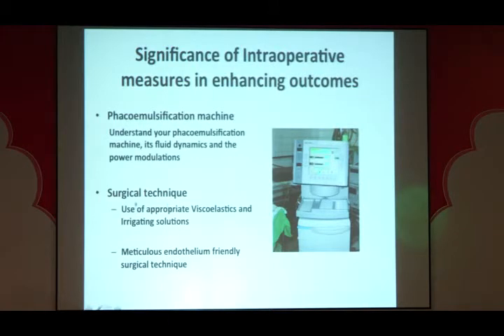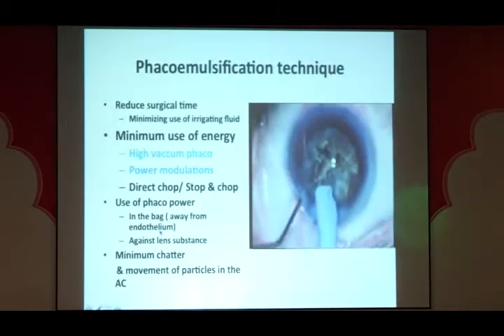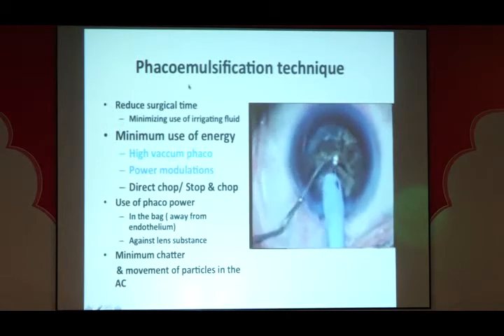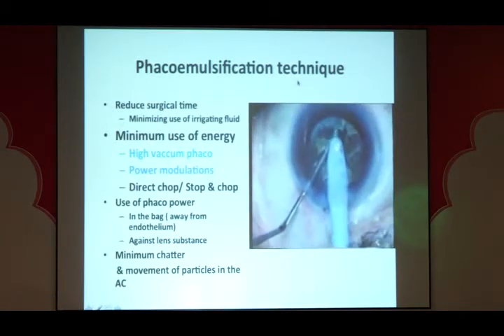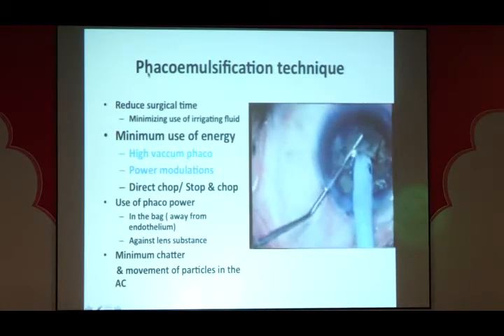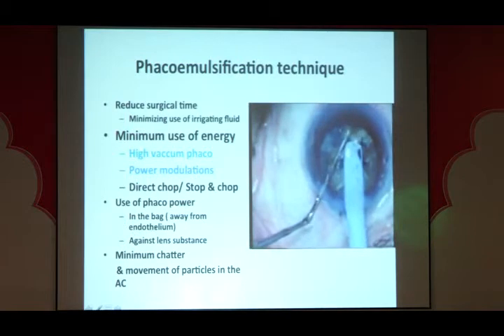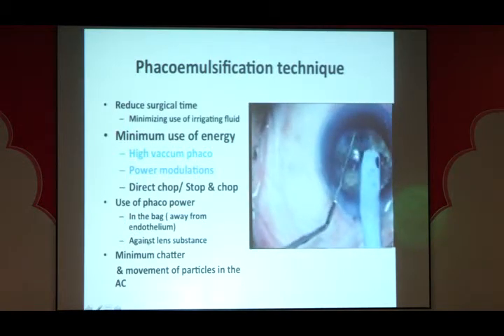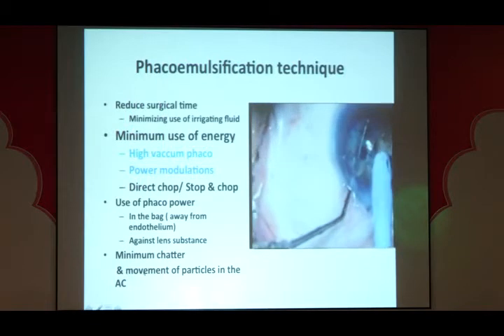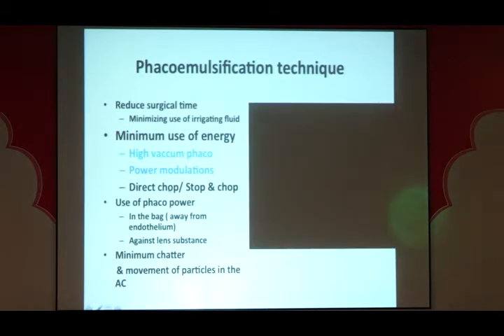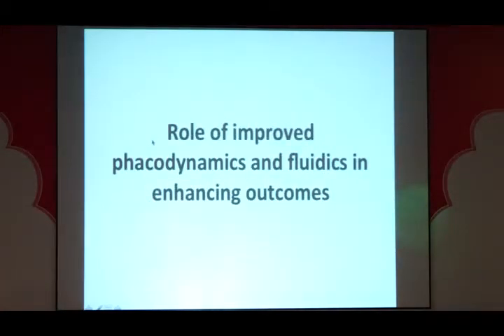Of course, there are other important measures in our surgical technique which we need to look at. For modifying our phaco-emulsification technique in the best interest of the patient, we need to reduce surgical time. We need to use phaco power away from the endothelium and have minimum possible chatter and movement and have a high followability. And how do we get that? How do we reduce the energy? By using a high vacuum phaco and using power modulations which make it possible for us. So let's see how the improved designs of the phaco-emulsification machines are helping us to do that.